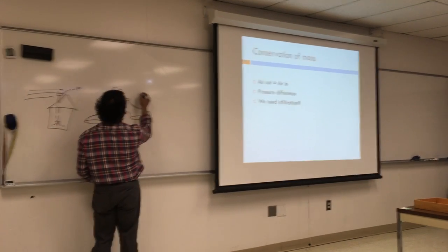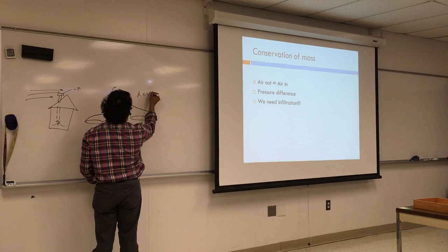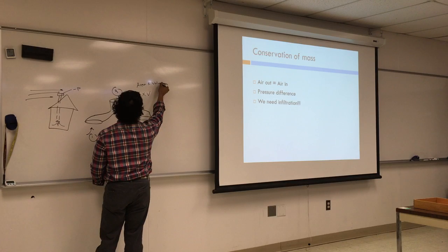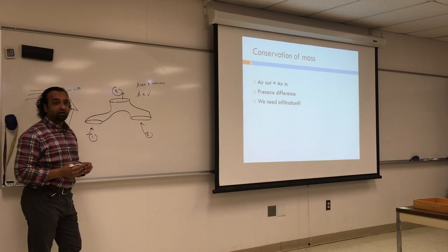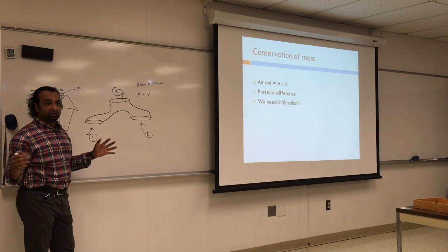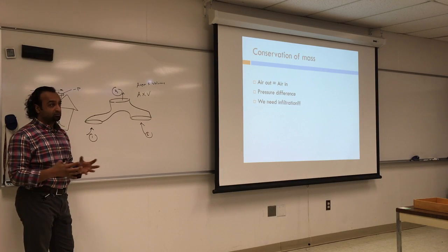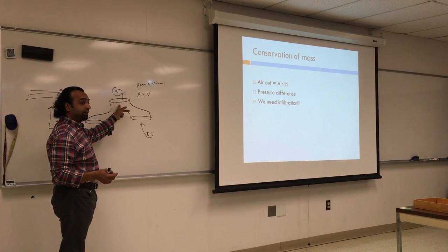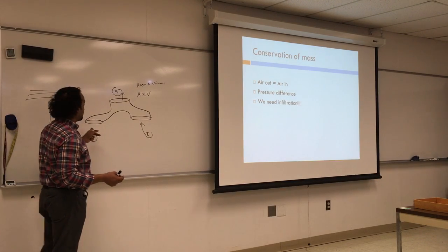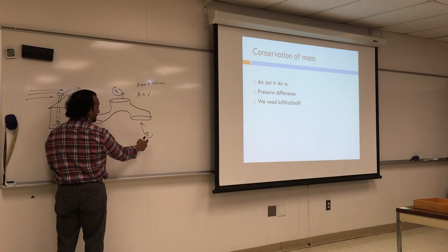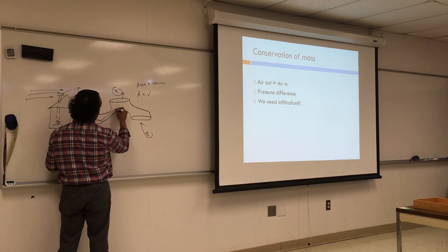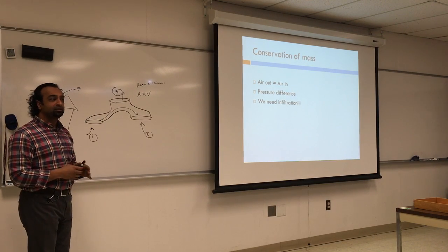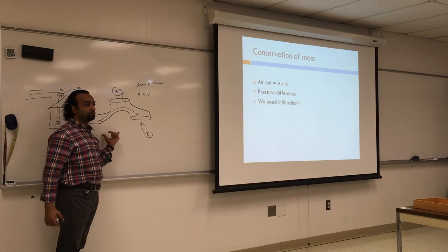We said before, flow rate is area times velocity. Granted that air is compressible, so it will change density based on temperature, right? But if the flow rate coming out of here is less than the total flow rate between 1 and 2, you will have the flow coming all the way here to here and not to here. So just to make things simpler, this opening should be larger than the total areas of both openings.